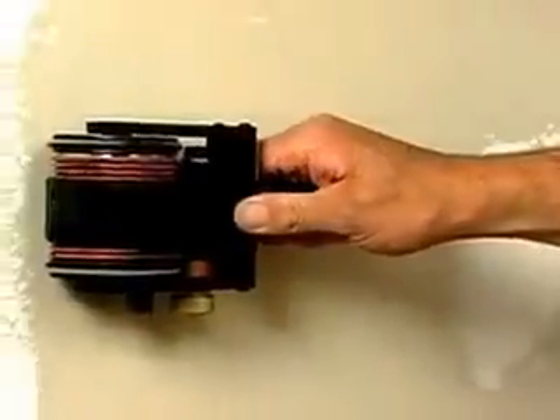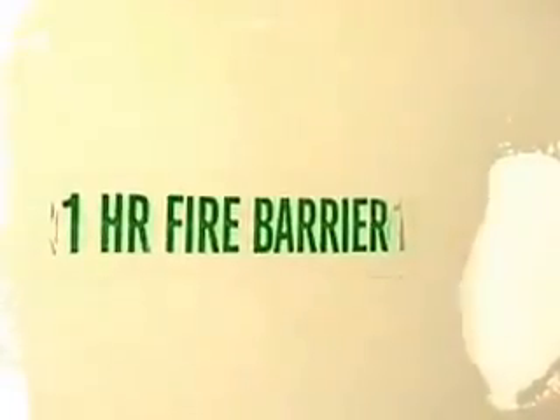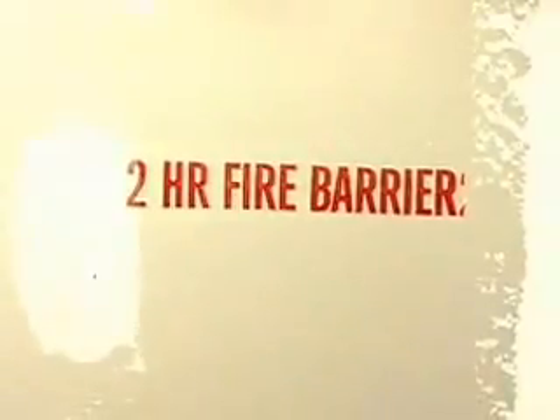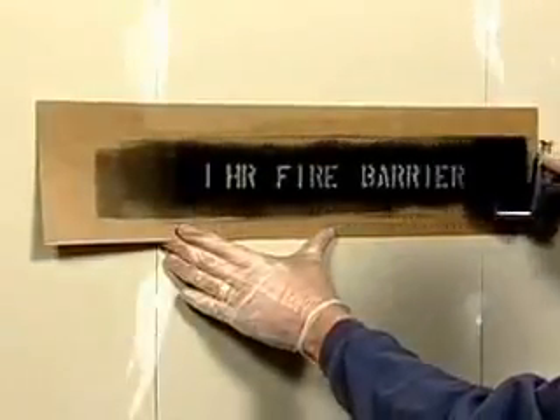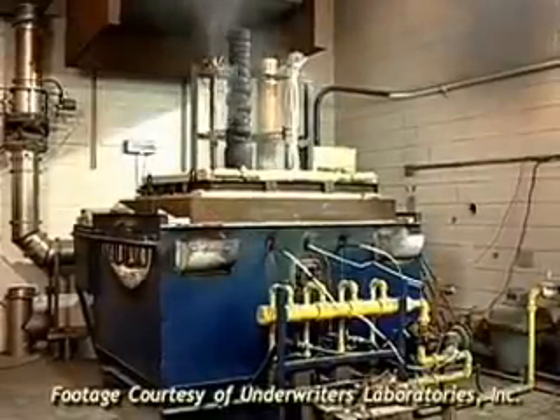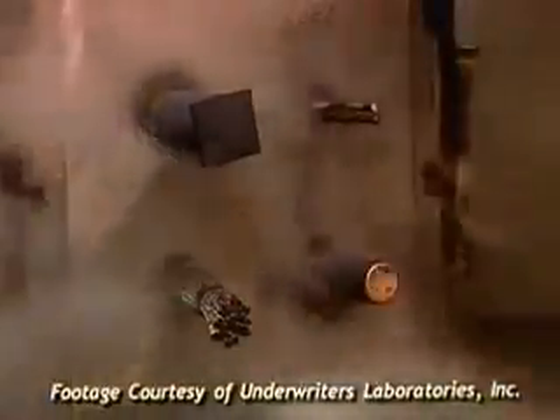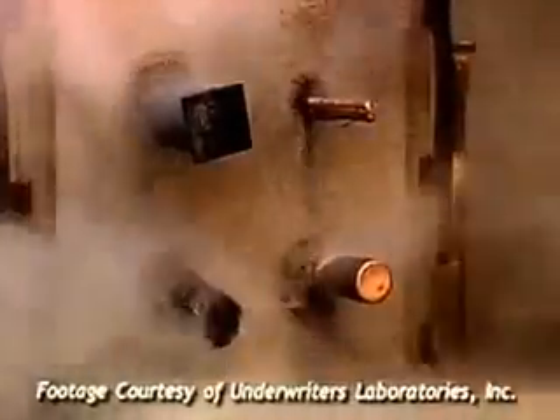Most of us are familiar with the terms smoke barrier and fire barrier, but understanding the differences is the critical first step in properly sealing openings in these barriers. A fire barrier is defined as a wall or floor designed to prevent the products of combustion from spreading vertically or horizontally for a period of 1, 2, 3, or 4 hours. Additionally, a fire barrier must be tested by a third-party laboratory, such as UL, to very rigorous test standards.